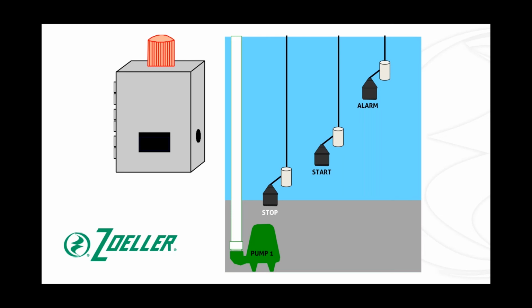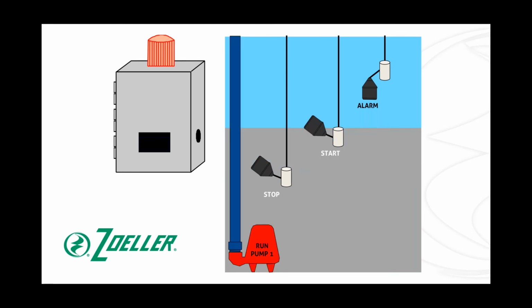In this sump pit, you can see we have one pump. The water level, shown in gray, has not yet risen high enough to activate any of the float switches. Let's run through this: water starts coming into the pit, and the first float, our stop float, is activated—nothing happens. Water continues to come into the pit, and as the level rises high enough, our start float switch is raised. This calls for the pump to be activated, and the pump begins pumping the water level down.